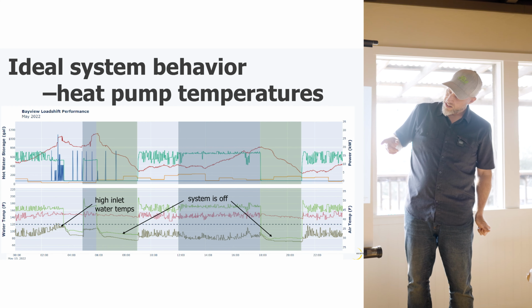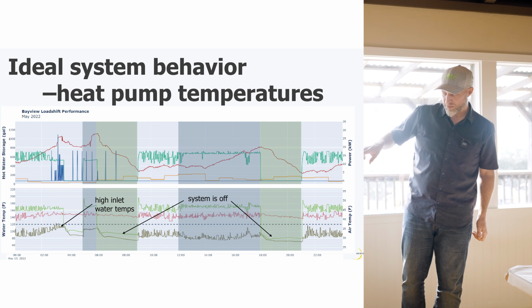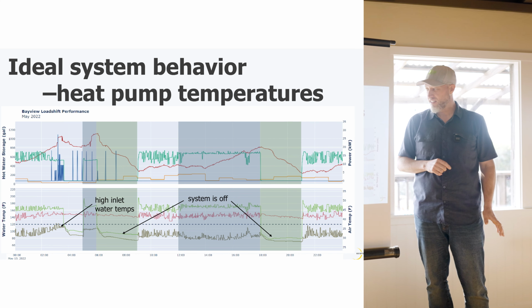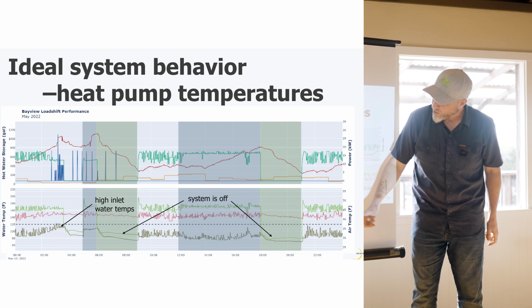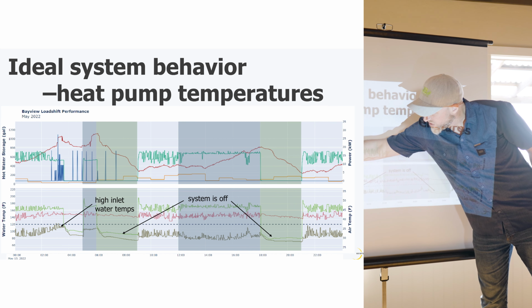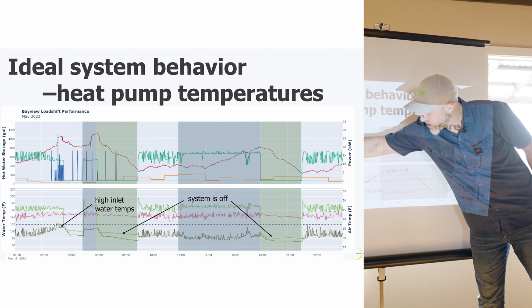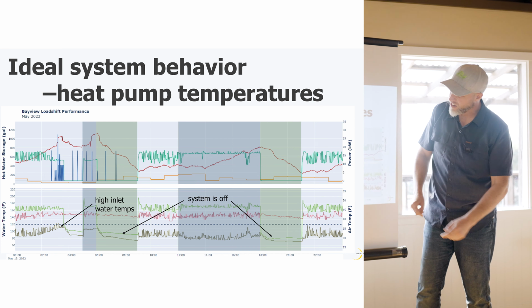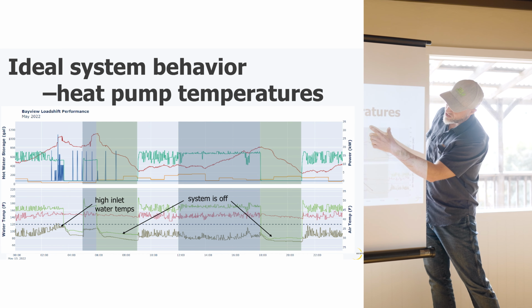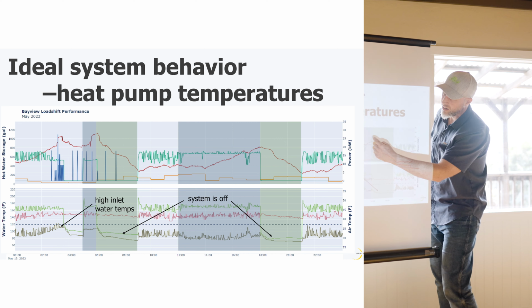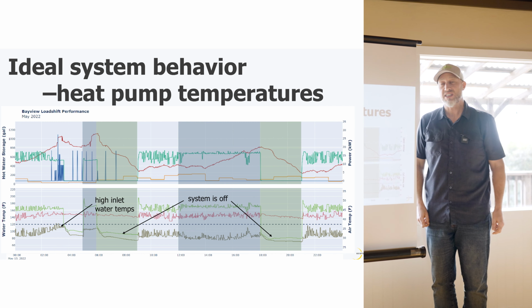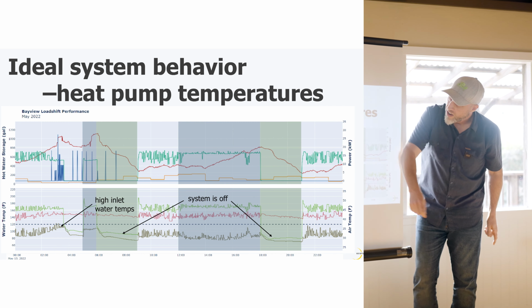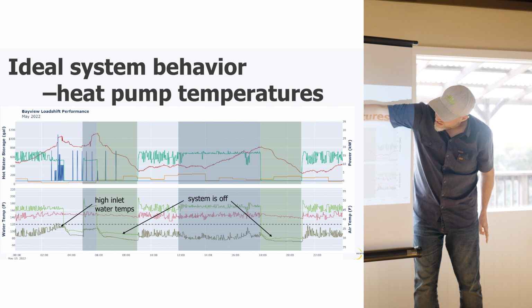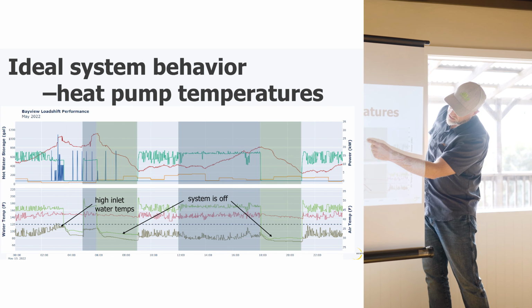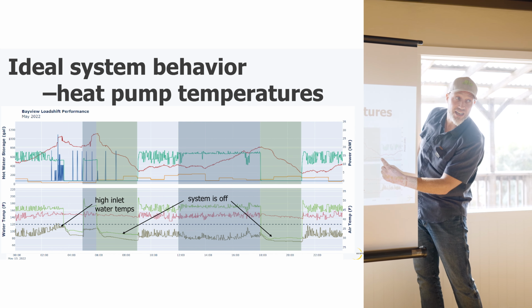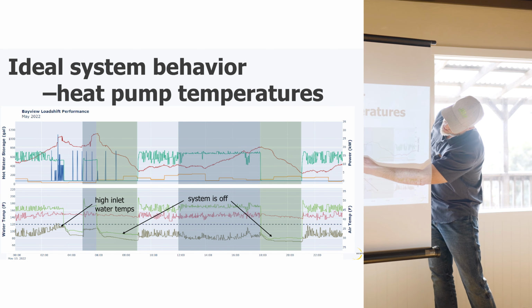Okay, so this is our load shift - I'm going to study this a little bit, but there's a lot of data here, so I'll show you what's going on. The axis over here is the hot water storage, and that's the red line, so you can see this is over a 24-hour day. These are our load shift periods, 4 to 9, and then the morning, 7 to 10 or 6 to 9, somewhere in there. The storage is the red, and you can see during our load shift peaks we're drawing down the tanks. The green is the input to the heat pump.